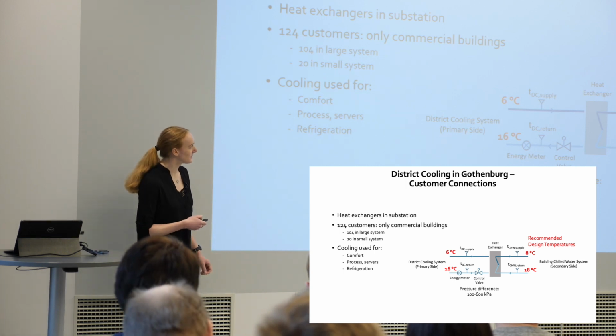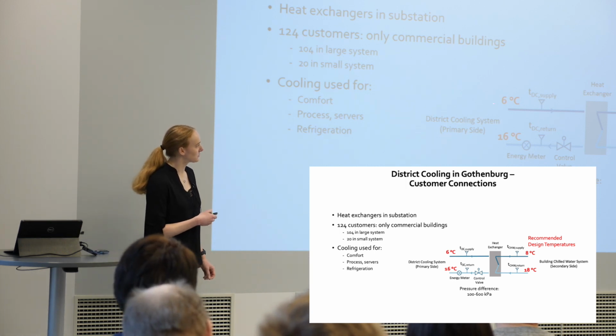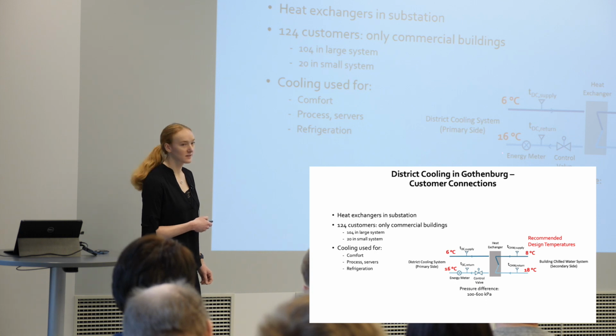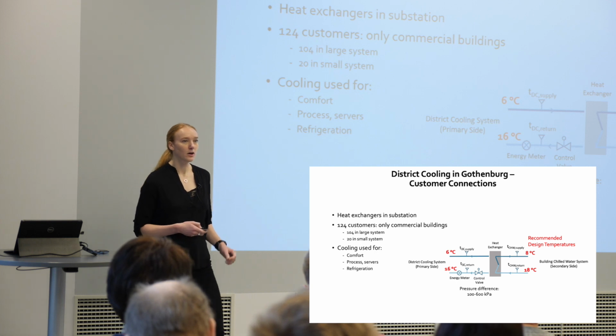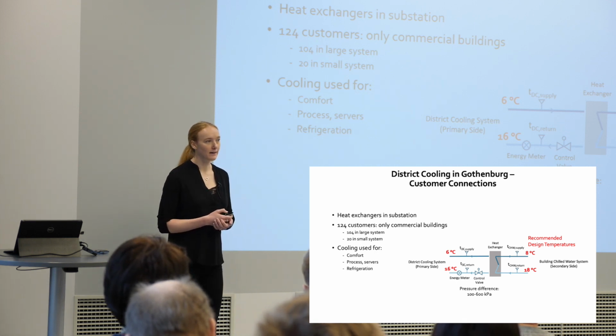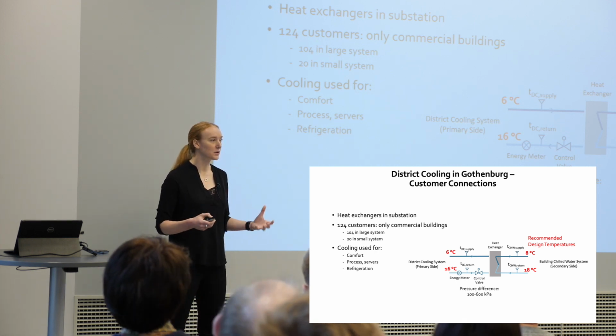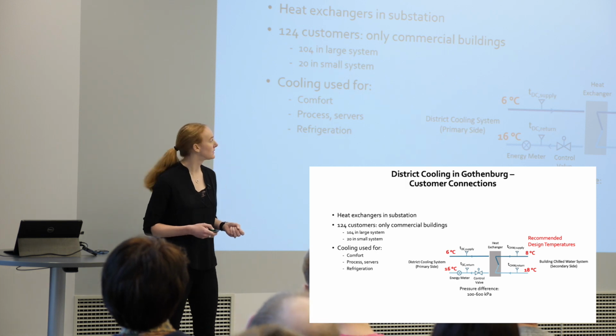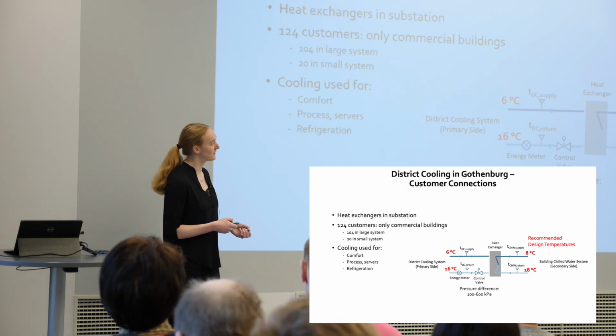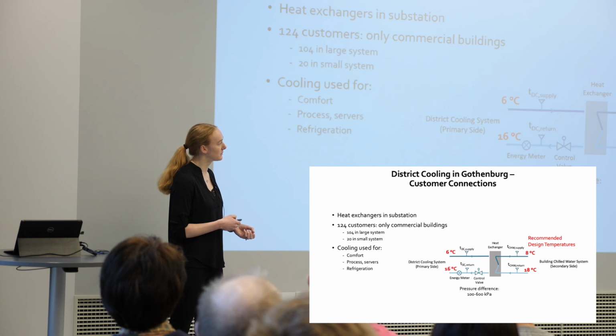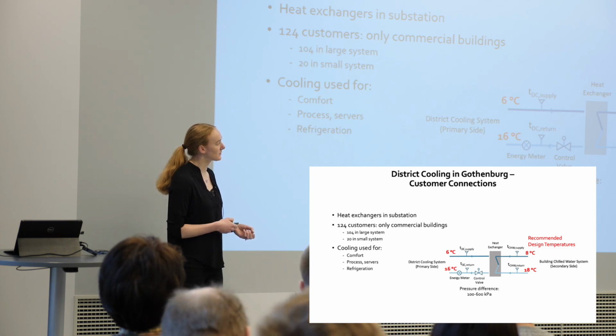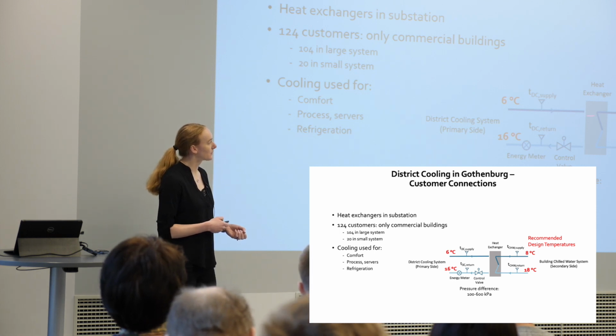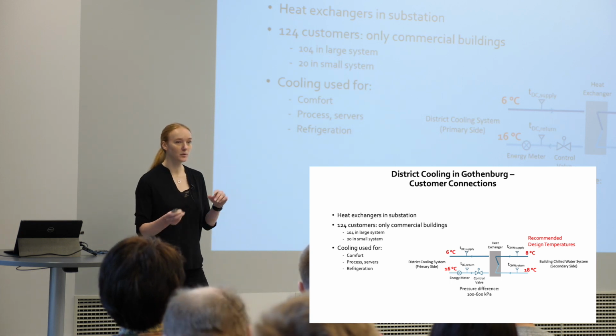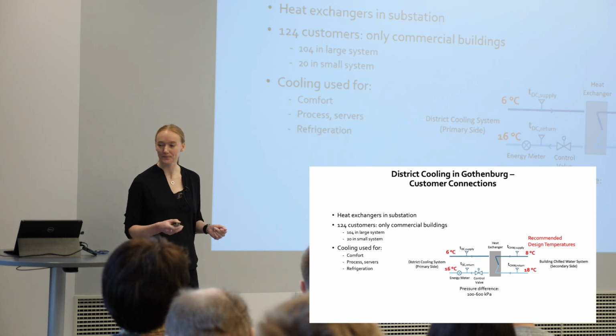So this is what the district cooling system has been designed for, as I mentioned before: 6 degrees supply. They want 16 degrees back. And based on these temperatures, there are recommended design guidelines for all district cooling systems in Sweden that suggest that the buildings should have 8 degrees supply temperature, and they should return 18 degrees. So you allow for a 2-degree temperature approach across the heat exchanger between both supply and return streams.